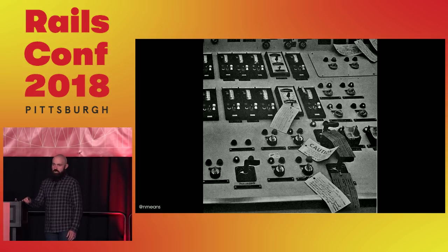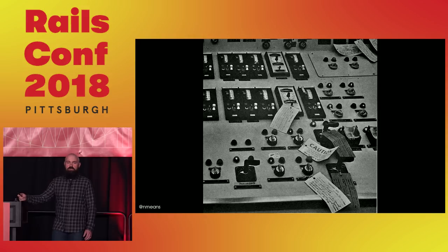And so Bill Zewe, assimilating all the information he had at his disposal and considering the full pressurizer, left the block valve open, so that in case the pressurizer did go solid, the pilot-operated relief valve could still respond if there was a pressure spike. He left the block valve open in an effort to keep the plant safe.